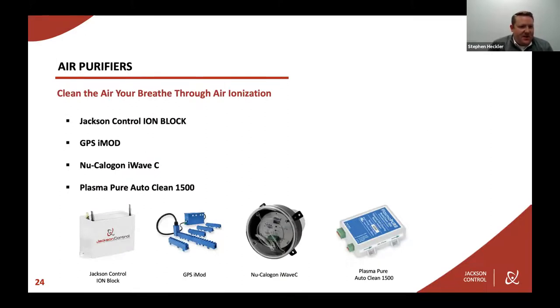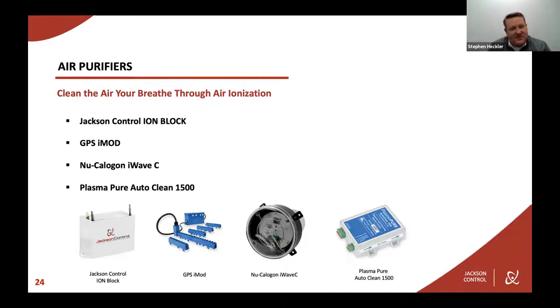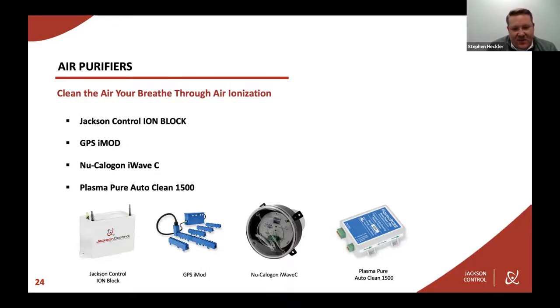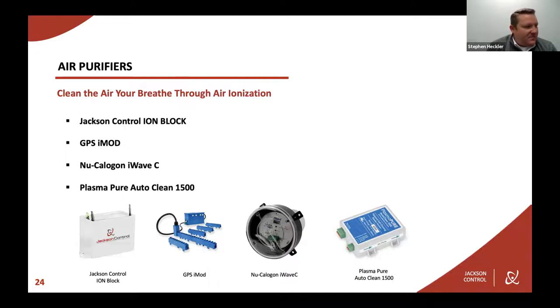The four options: Jackson Control's ion block can treat up to 2,500 CFM of airflow, and you size it according to your CFM. If you have 25,000 CFM, you simply put 10 of those in the airstream. There are also products from GPS, NuCalgon, and PlasmaPure — they each do slightly different things. They can come in NEMA 4 casings, have analysis capabilities, connect to building automation systems, and be set to auto-clean or automatically come on and off — whatever you need for your facility.